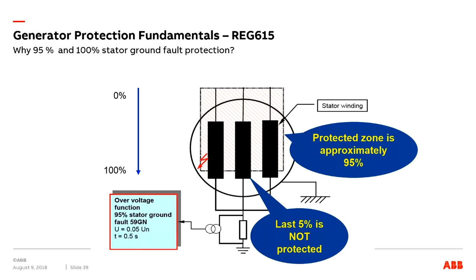However, detecting a ground fault close to the generator neutral is very critical or crucial for a large machine. So maybe up to medium-sized machines, the last 5% can remain, but it is always good to have 100% stator ground fault protection. By using the normal methods, we can protect only up to 95% of the winding. So we need to have additional protection to cover the last 5% of the winding.